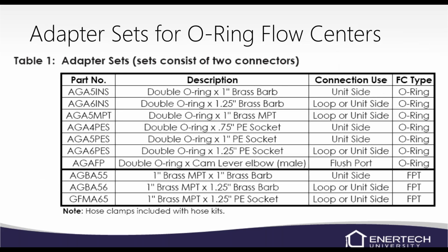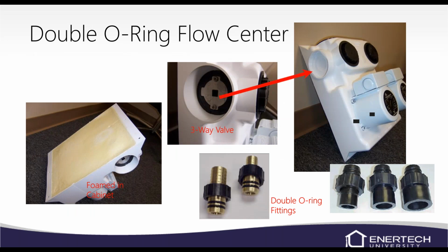Let me go back to this picture here of this flow center. We see where that arrow's at. Well, if you stick it real close in a corner on a wall, you're not going to be able to get your ratchet in there to put that 3/8 drive into that hole and turn it. You may be able to get one in there, but then you've got to get your head on the side to be able to see where those little notches are so you know it's open and closed. So make sure you've got a little bit of room there.